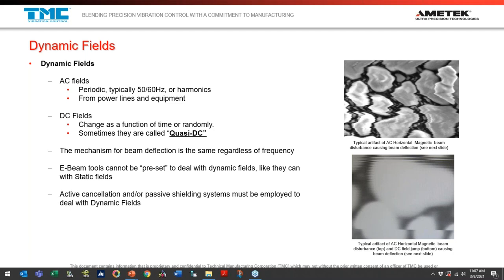On the right-hand side we have a couple of images. The top image shows a very common swaying back and forth at a relatively high frequency — very typical of what you'd see with an AC magnetic field disturbance horizontally. In the lower image, you see that in the top half but also a DC shift happening — an instantaneous shift of a DC field that suddenly wasn't there and then very quickly was. That's what you'd see from an e-beam tool turning on in a nearby environment — that rapid shift in DC shows up in the image.